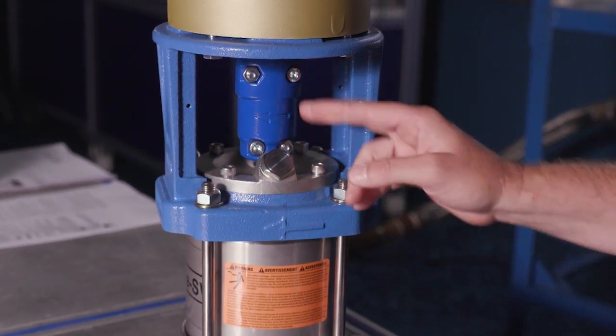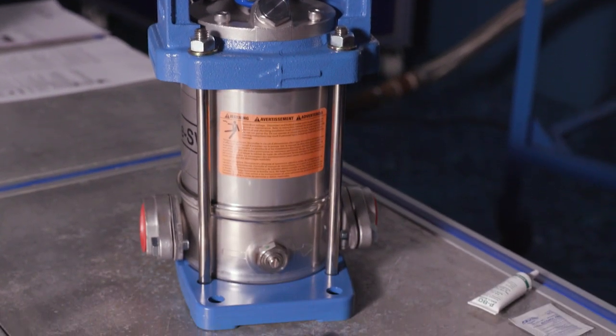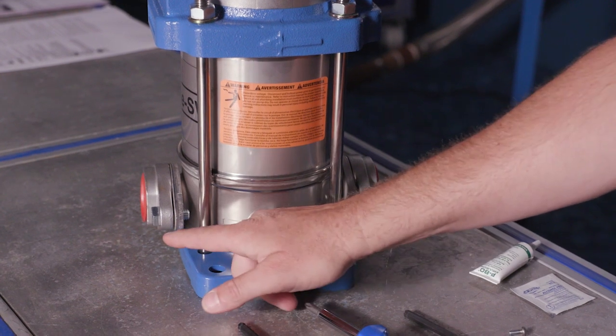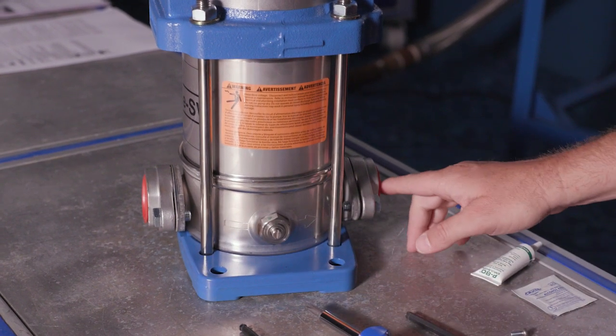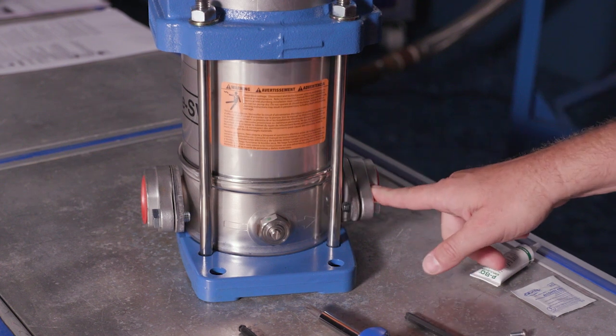We want to make sure that the rotation is following the arrow. Notice these two are the same rotation. This arrow here is flow. We can see here that on the left is my input and on the right is my discharge, or suction and discharge on the right.